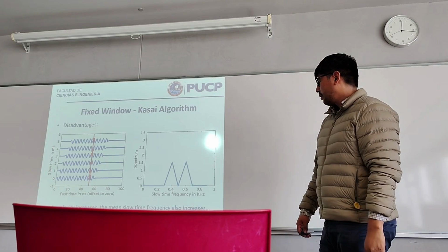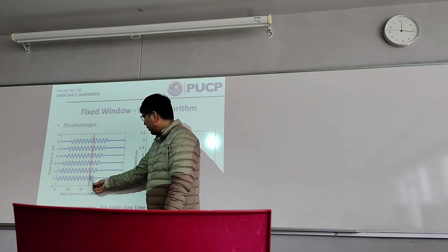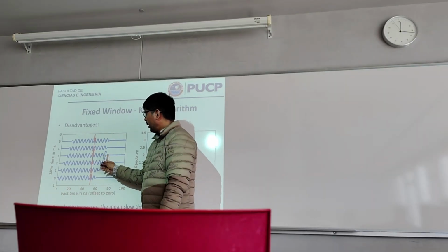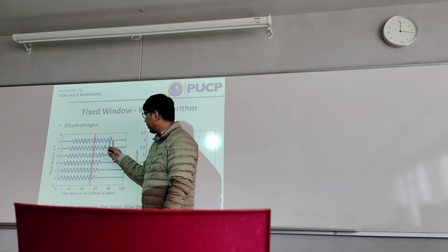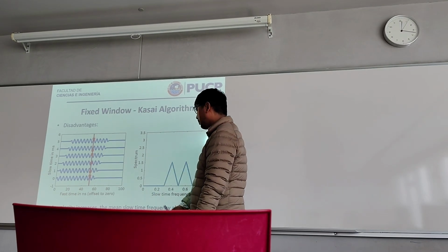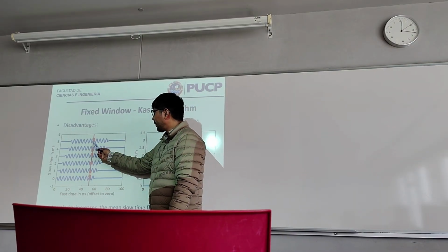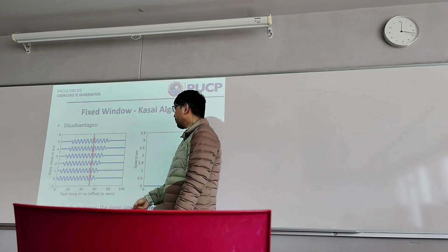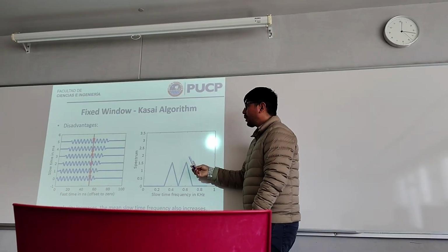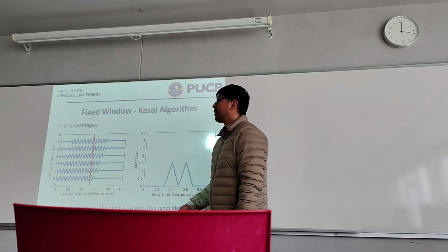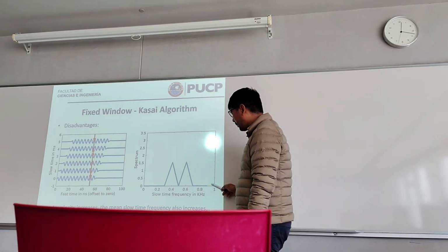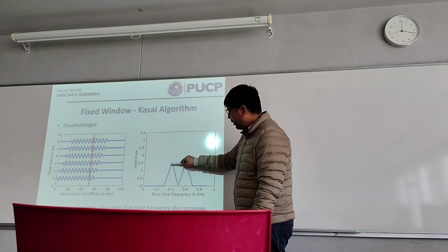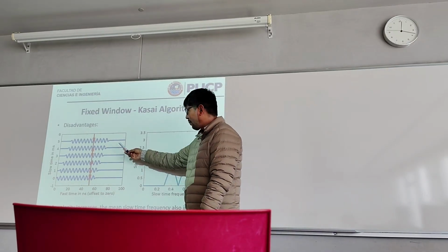Also, as velocity increases, imagine that this represents some movement of the particles, a red blood cell, for example. It makes changes in the echo at different slow time samples. So, analyzing these samples, we obtain a velocity. If the velocity is larger, we will probably see more change across different slow times. And we saw that if we calculate the Fourier transform of this slow time signal, we obtain a spectrum in the slow time domain with some sampling frequency. This maximum frequency will be associated with the velocity of the particles that are moving there.